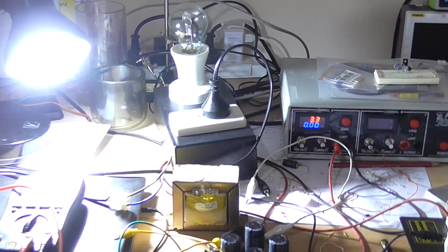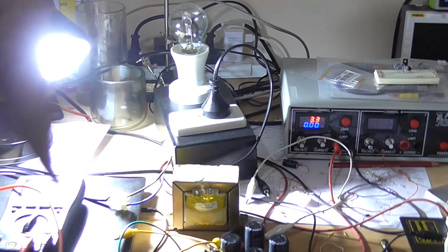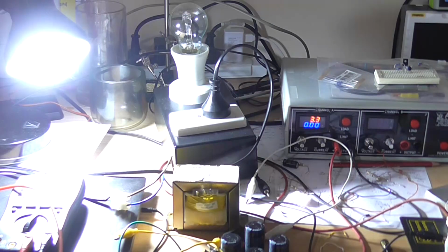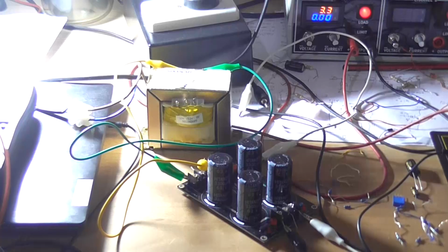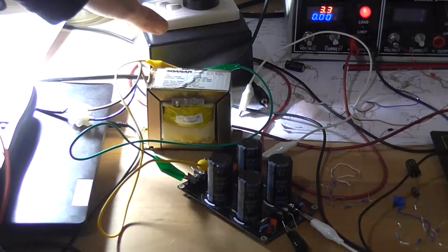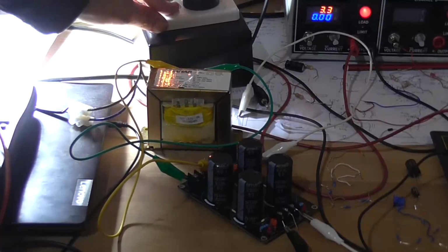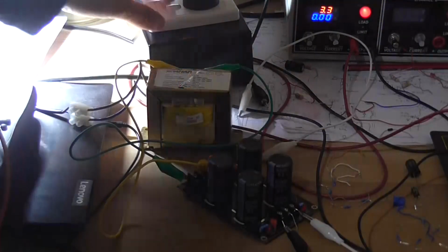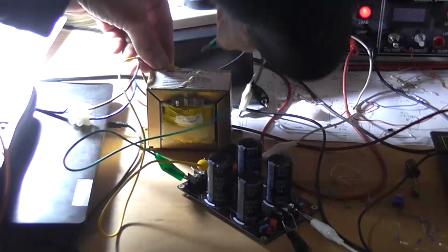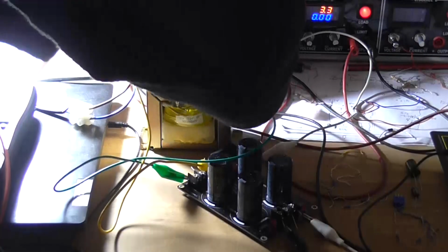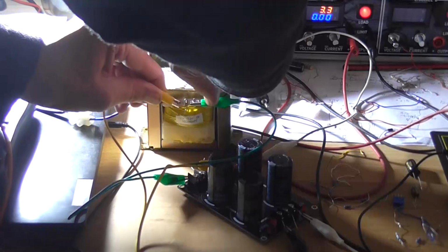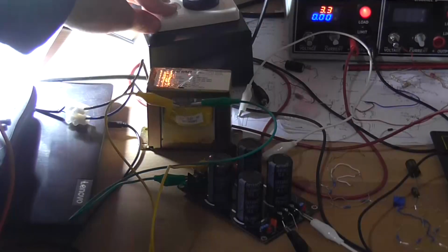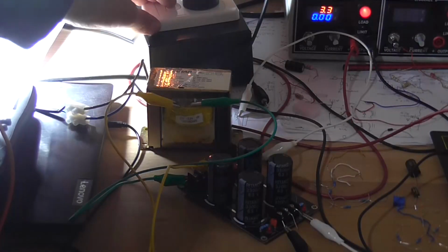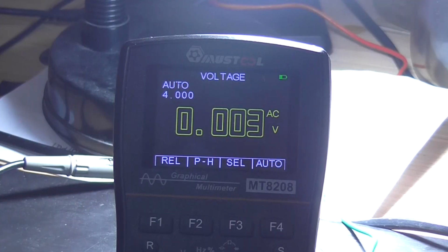I will hook it up to the DC supply, but only from the 15 volt to the 0. Okay, I've got the transformer hooked up to one secondary side on the 15. Nothing. Put it to the other secondary side. Nothing. I'll do an AC output test instead.